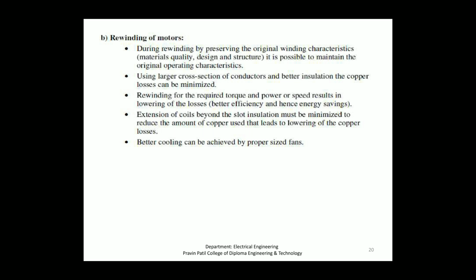Rewinding of electric motors when they fail can be a cost effective option in many ways. While the rewinding process is expected to be extensive and capable of bringing the motor back to like new condition, most rewinders do not follow every step or the precision needed in every step of rewinding. This has a major impact on the efficiency of a rewound motor. Rewinding will decrease the efficiency by 2 to 5% in most motors.